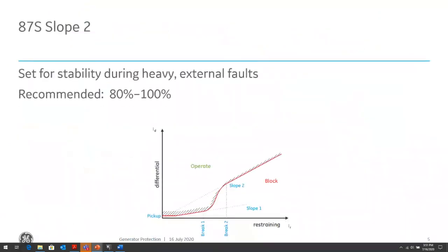So, what about the slope setting itself? The slope setting is applicable for the restraint current, again, above breakpoint 2. This slope is set to ensure stability under heavy external fault conditions that can lead to high differential currents as a result of CT saturation. So remember, the relay looks at differential over restraint. So the higher the slope, the more differential current the relay could deal with without tripping. And that's what happens during a saturation condition, we see more differential than restraint.